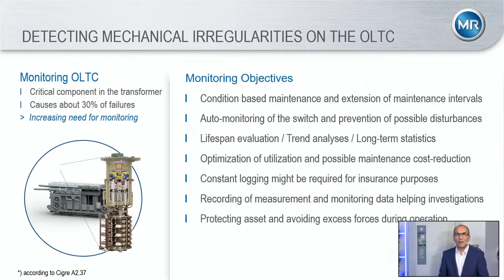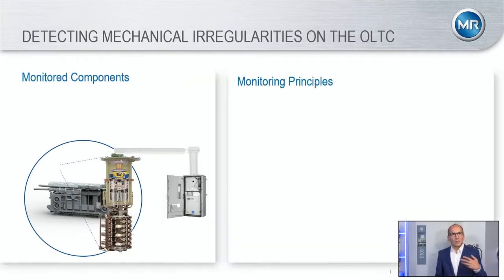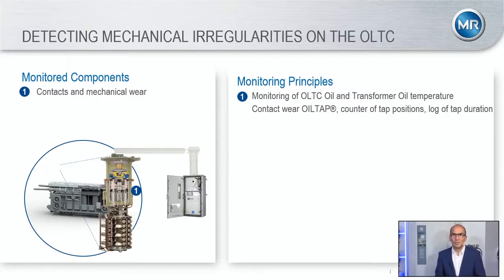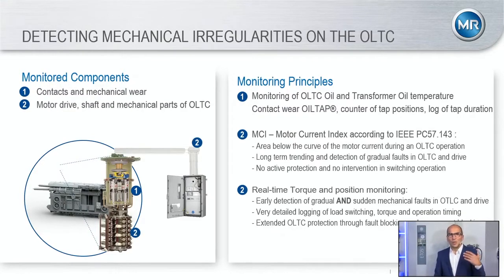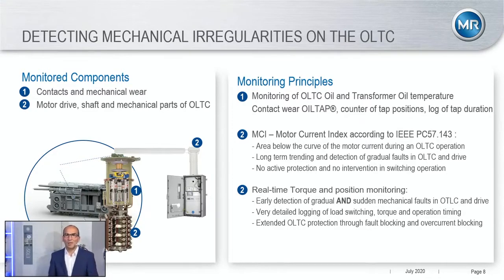We have multiple monitoring principles which we use on the OLTC. The first principle is to ensure the contacts and the mechanical wear are in good shape — for that MR has been providing the oil tap guard and various monitoring capabilities. The second aspect is to monitor the entire mechanical part, which gives a good understanding of the wear and care of the motor drive unit, the shaft, and the mechanical parts of the OLTC.